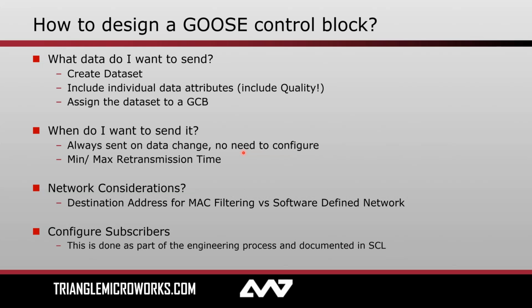Now, a higher max time will make it less likely that I have a communications interruption and have lower bandwidth on the network, but it will also take longer before I do detect a potential network interruption. And again, common values for these are maybe 2 milliseconds for min transmission time and 10 seconds for max.